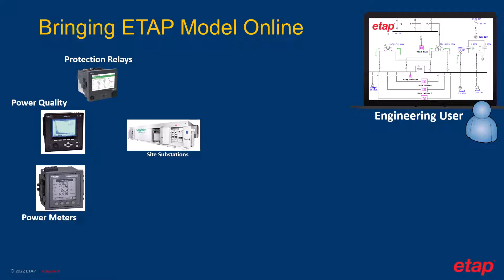Now, to get ETAP online, we add a data collection server to the site. These data collection servers use the existing power infrastructure on the substation to establish direct communication to power automation devices. Our ETAP data collection server can handle many common communication protocols for devices, such as IEC 61850, Modbus, DNP3, just to mention a few.